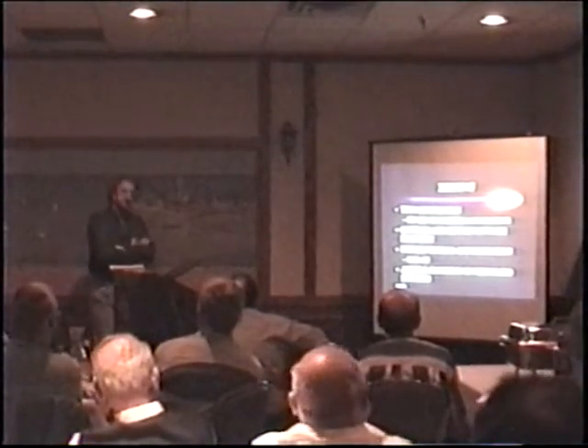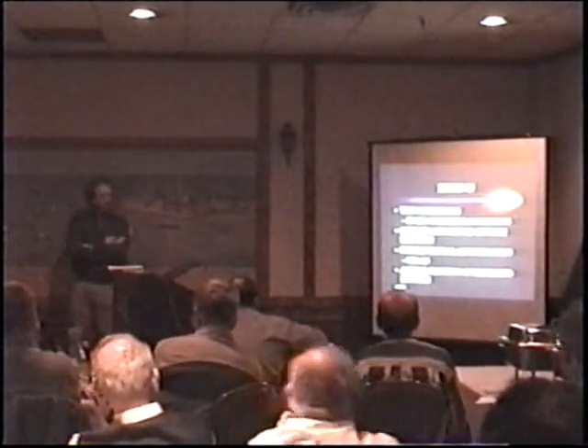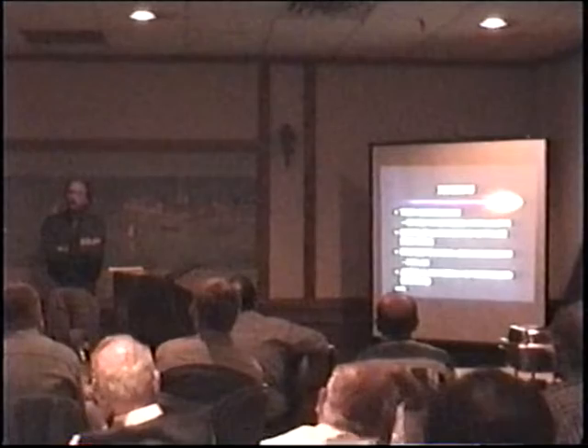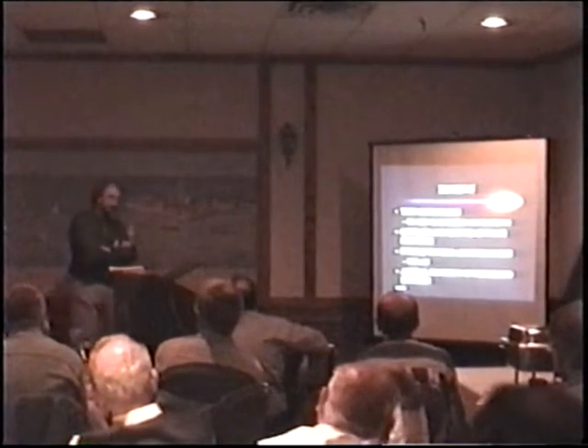You have to be concerned about future testing and inspection. NFPA 25 covers that from A to Z. Of course, your AFFF should be tested on an annual basis. Sent into a lab, they'll do a number of performance tests to make sure it still makes a film, puts out fires, and does all the good stuff it's supposed to do.